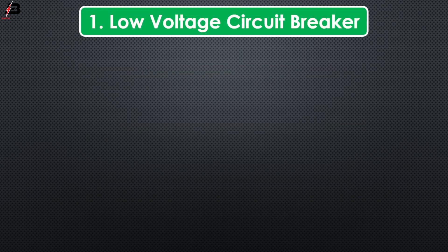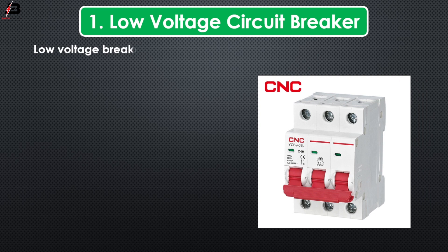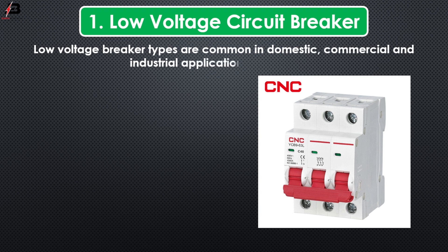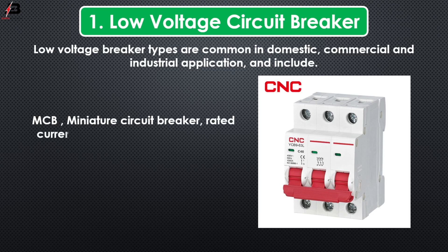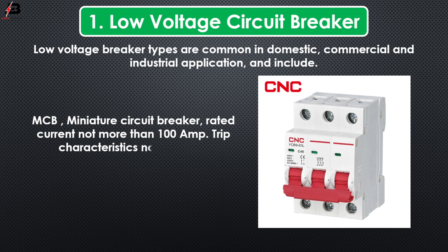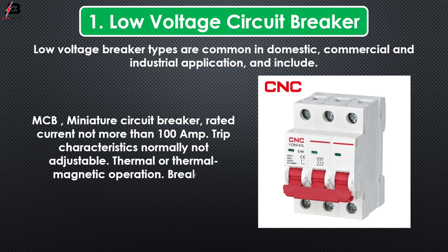Low voltage circuit breakers. Low voltage circuit breaker types are common in domestic, commercial, and industrial applications and include MCB — Miniature Circuit Breakers. Rated current not more than 100 amperes. Trip characteristic normally not adjustable. Thermal or thermal magnetic operation. Breakers illustrated above are in this category.